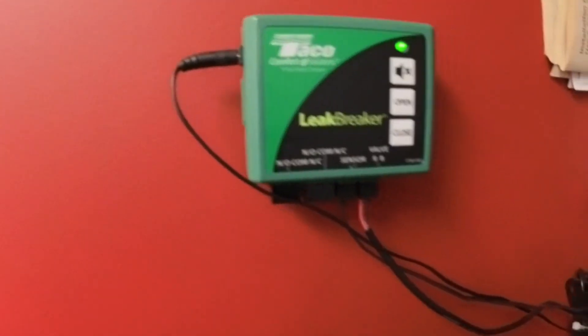We're going to test it — press the close button and if you watch right here you'll see the valve turn and close. There we go. Now we'll open the valve. I like to exercise it because if you don't, it can get corroded from the water and it will stick. So I like to exercise it regularly.